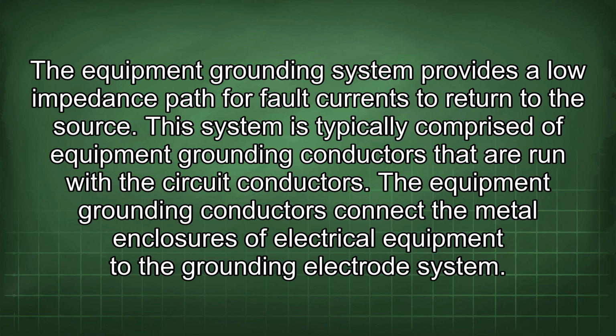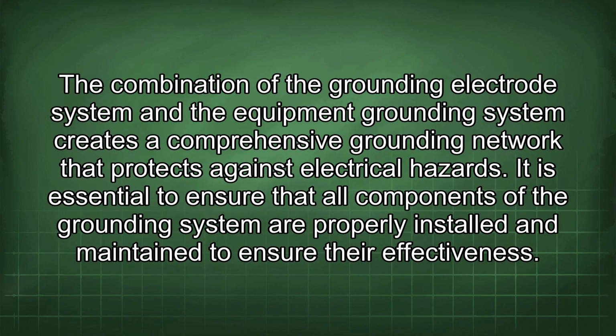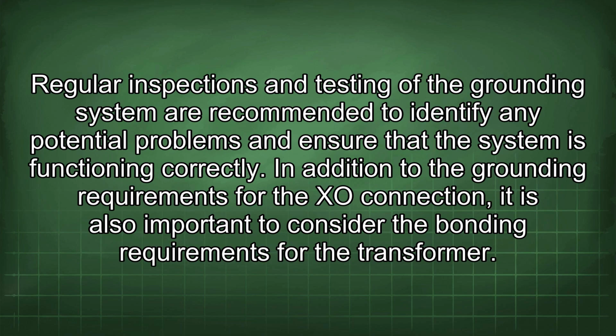The equipment grounding system provides a low impedance path for fault currents to return to the source. This system is typically comprised of equipment grounding conductors that are run with the circuit conductors. The equipment grounding conductors connect the metal enclosures of electrical equipment to the grounding electrode system. The combination of the grounding electrode system and the equipment grounding system creates a comprehensive grounding network that protects against electrical hazards. It is essential to ensure that all components of the grounding system are properly installed and maintained to ensure their effectiveness. Regular inspections and testing of the grounding system are recommended to identify any potential problems and ensure that the system is functioning correctly.